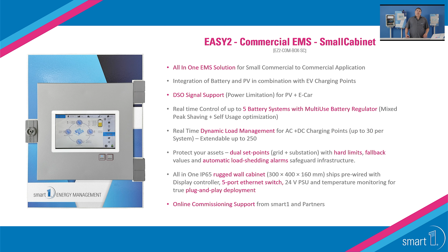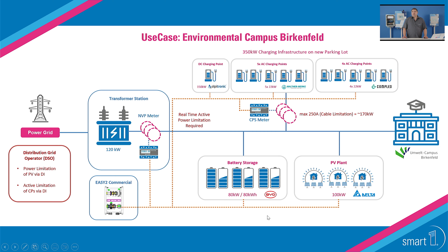So switching back to the environmental campus Birkenfeld. Based on the requirements that we had, the first thing that we needed to do is, again, install measurements. So we installed a meter on the NVP connection point. The client installed a meter on the CPS connection point. And the next thing that happened is they installed the EASY2 commercial cabinet. This EASY2 commercial cabinet is then connected through Ethernet with the meters, to the charging stations, to the batteries, and also to the PV inverters. And what the system does, in addition, is directly take the digital input signals from the DSO, from the grid operator, inside this box for the external control.